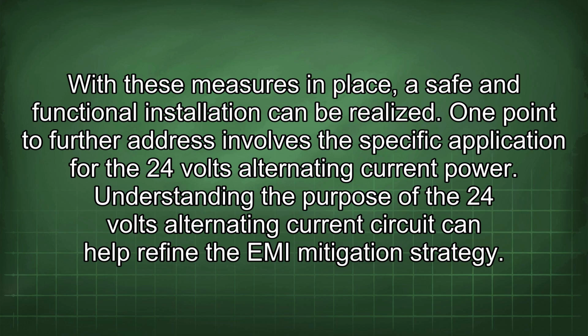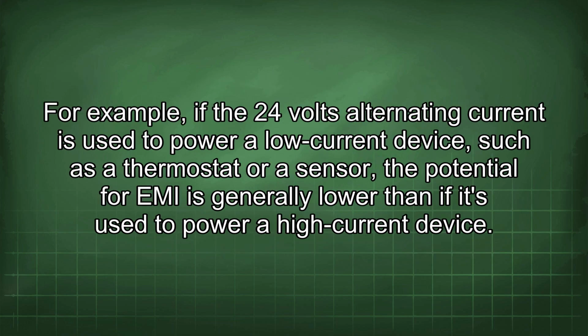One point to further address involves the specific application for the 24 volts alternating current power. Understanding the purpose of the 24 volts alternating current circuit can help refine the EMI mitigation strategy. For example, if the 24 volts alternating current is used to power a low current device such as a thermostat or a sensor, the potential for EMI is generally lower than if it's used to power a high current device.